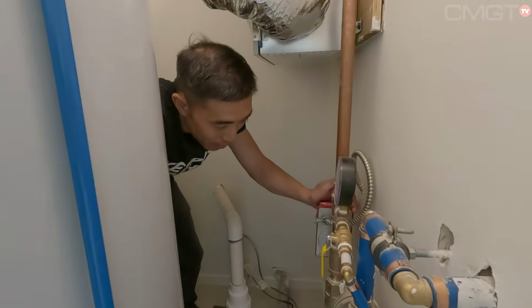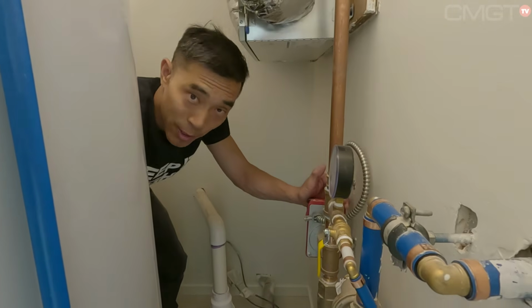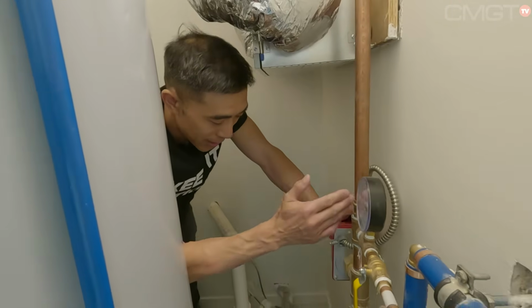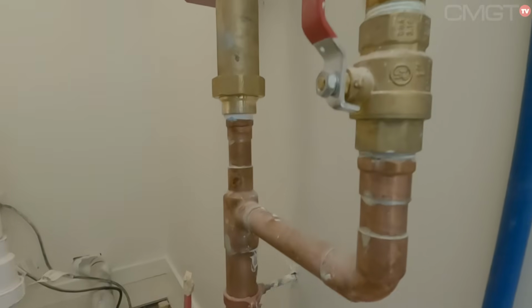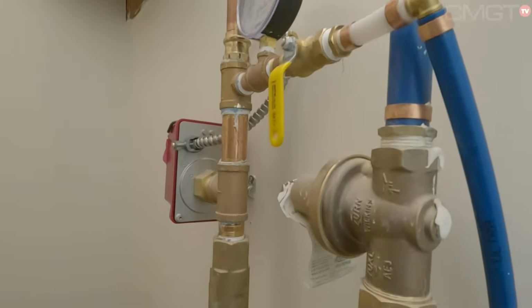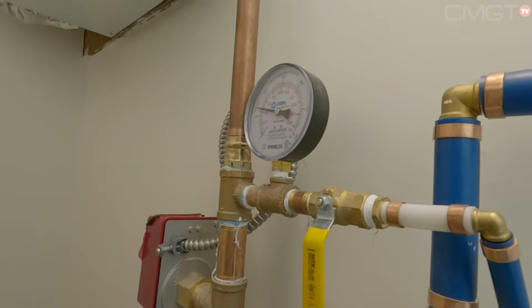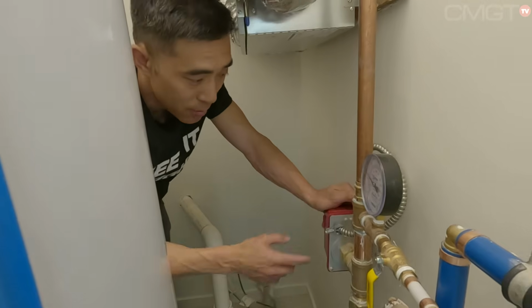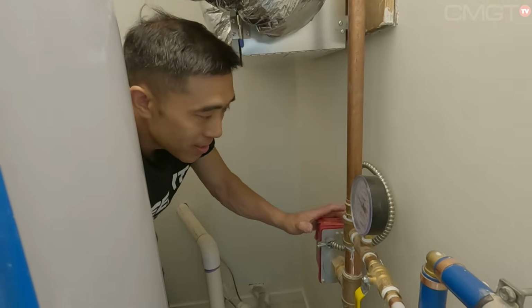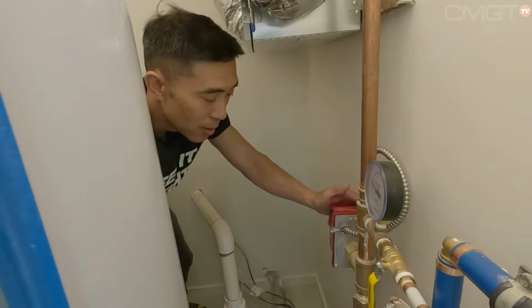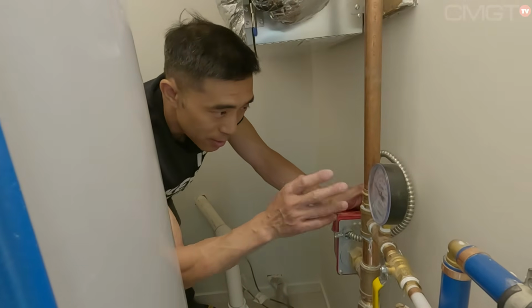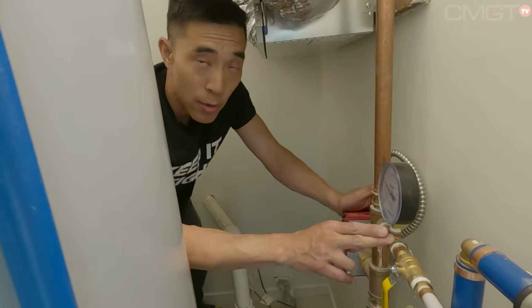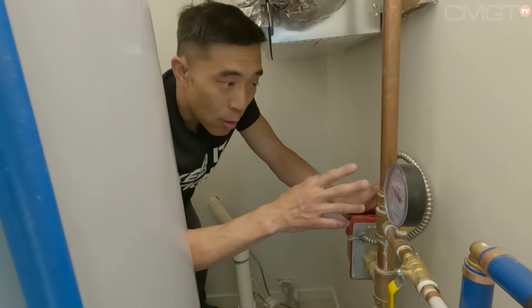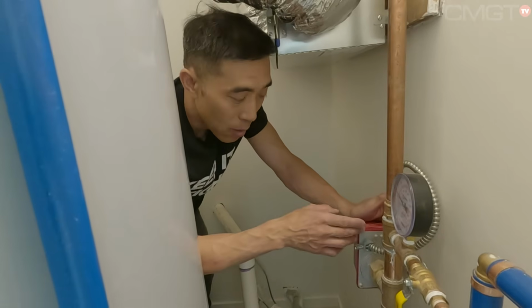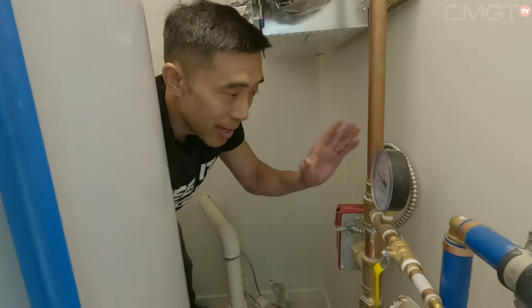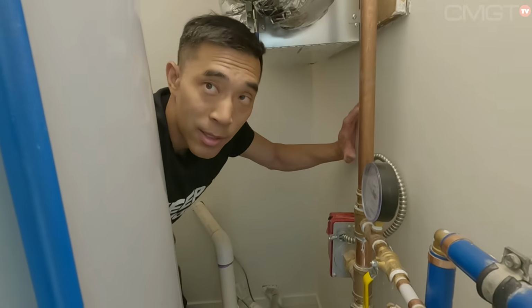Okay, so we're in the mechanical room right now, and I want to explain to you the life and safety feature of the sprinkler system. Okay, now note that the sprinkler system is in line with the main water line coming into the house, so it remains uninterrupted, except for the main valve. You also note that there's a gauge attached here that shows you the pressure that's currently in the sprinkler system, and this interlock device that connects the sprinkler system to the fire alarm system. So what this system does is, when this sprinkler system sees a drop in pressure as a result of the sprinklers going off, over the course of X amount of seconds, it will activate this interlock. And what this does is it activates all the fire smoke alarms inside the house.